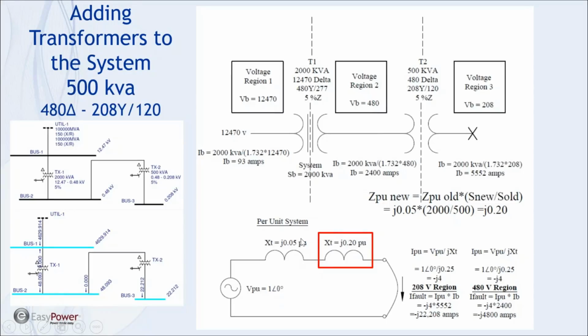As we take that transformer and put it into our per unit system, again, my base VA is 2000 kVA. I divided it now into 3 voltage regions: 12,470, 480, and 208. I have my 3 base currents calculated here: 93, 2400, and 5552. And again, here's my change of base calculation. I take my 5% on my 500 kVA transformer. To put it into my per unit system, I have to do a change of base on it from 500 kVA to 2000. So that becomes a multiplier of 4. And so now that transformer looks like a 0.2 per unit impedance.